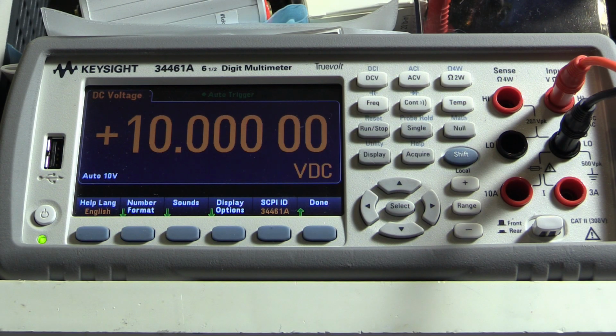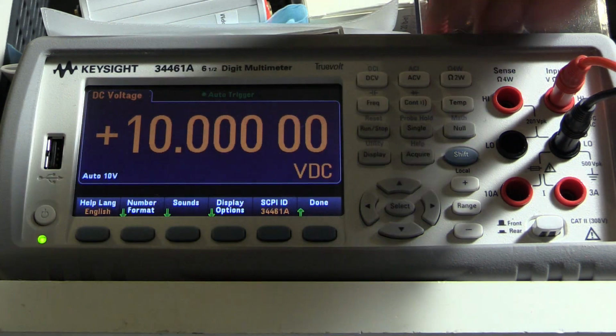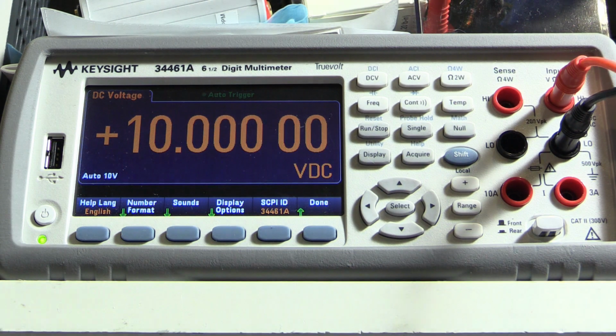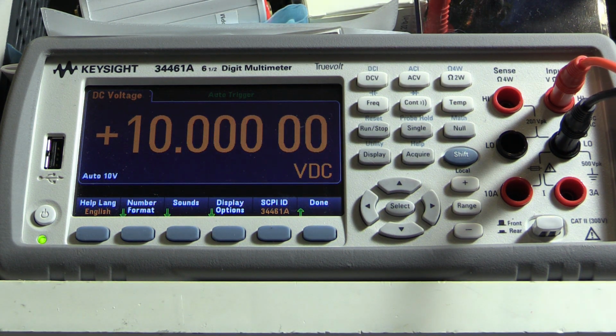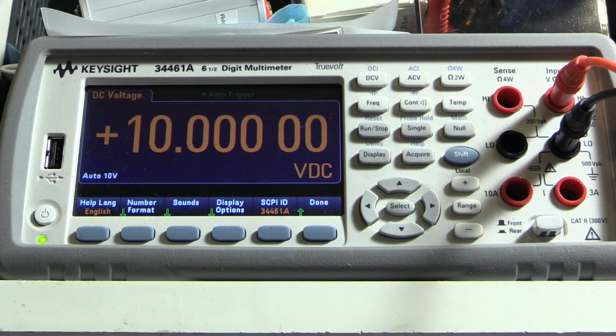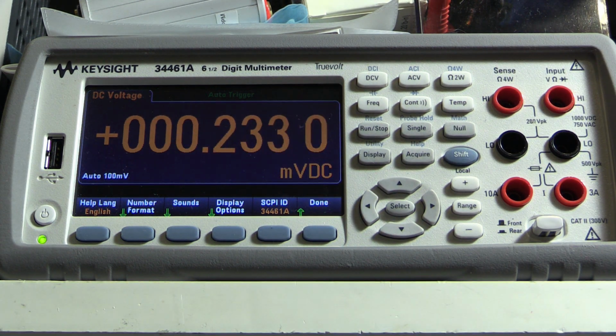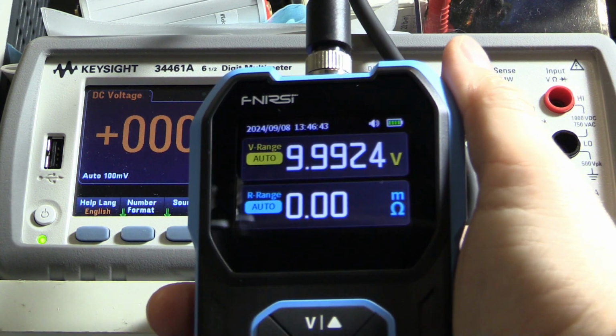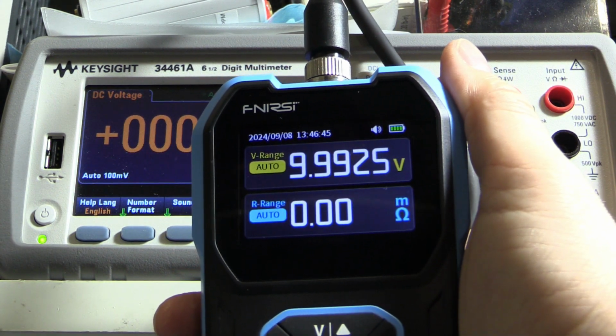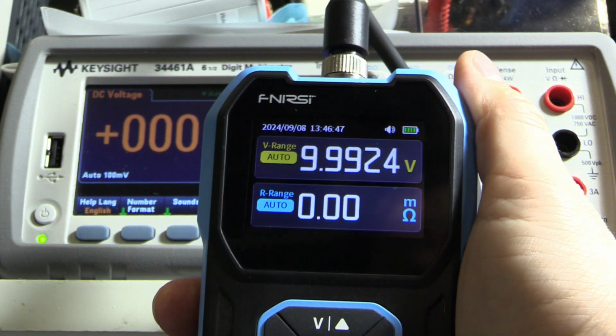All right, just for a quick voltage test, I've got the 34461A 6.5-digit multimeter here hooked up to my Fluke 731B 10-volt reference, and you can see there, exactly 10 volts. I've got the lights off, a bit shadowy because the screen's not so bright. And if I unplug it from there, hook it up to the battery tester, what do we get? 9.9924. Yeah, that's good. Not a problem at all. Voltage is accurate. Good job.